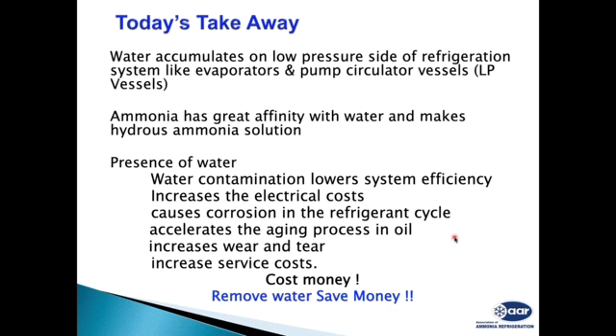On the water side, water accumulates on the low pressure side of the refrigerant system, like evaporators and pump circulator vessels. Ammonia has a great affinity with water. It makes a hydrous ammonia solution. Hydrous ammonia solution does not perform as per our standard pressure temperature chart, and it increases the ammonia temperature. So presence of water increases ammonia temperature, contaminates, lowers system efficiency, increases electricity cost, causes corrosion in the refrigerant cycle, accelerates aging of the oil, increases wear and tear, and increases the service cost and manpower cost. So again, it costs money. Remove water continuously, save money.